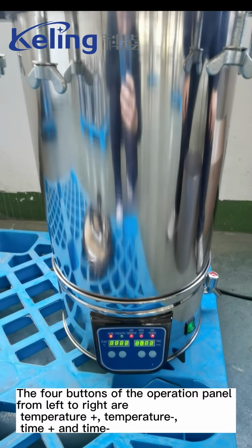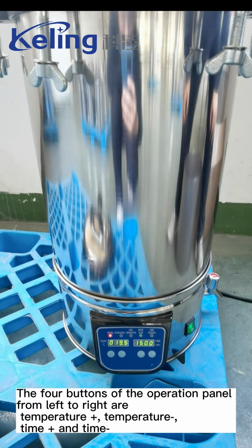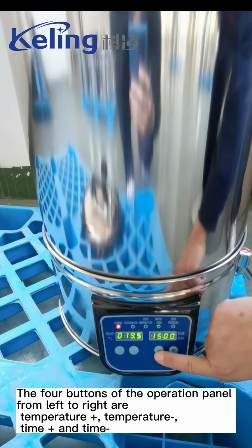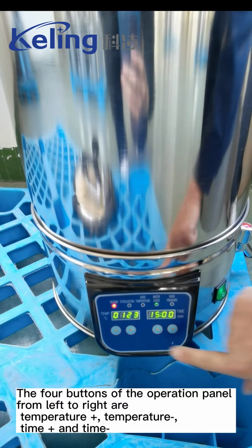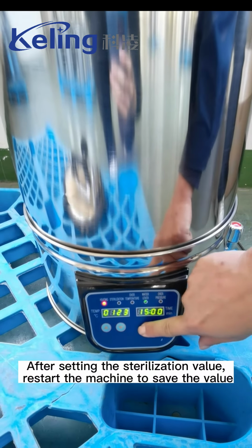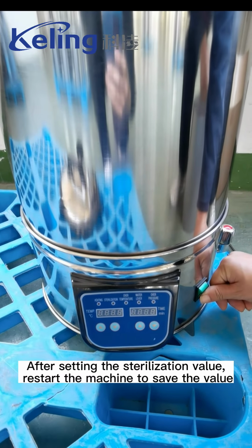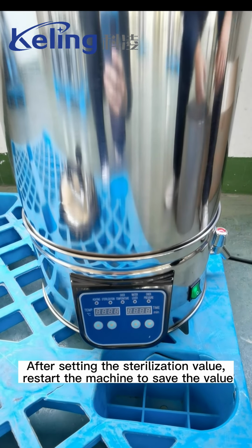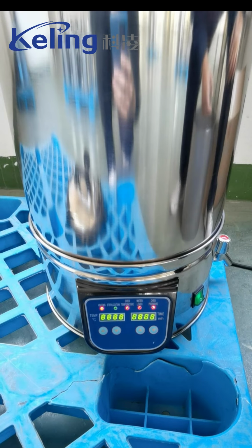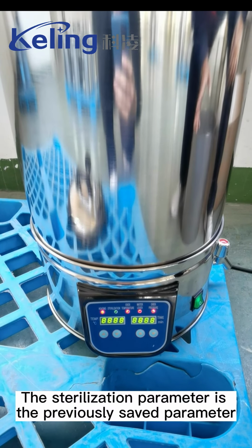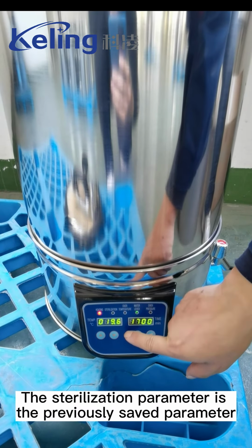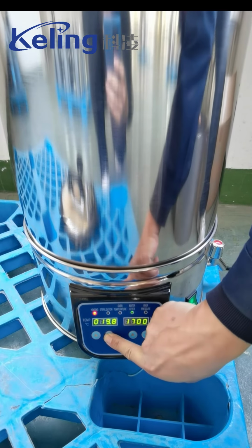The 4 buttons on the operation panel, from left to right, are: temperature increase, temperature decrease, time increase, and time decrease. After setting the sterilization value, restart the machine to save it. The sterilization parameter shown is the previously saved parameter.